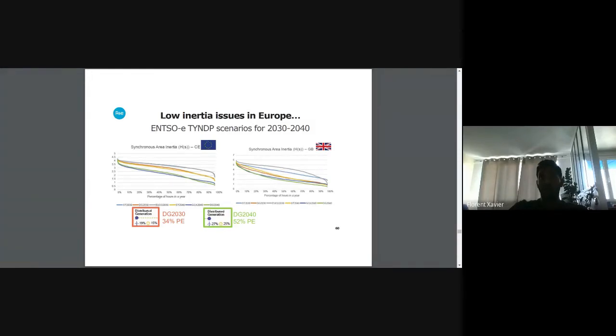The question is why grid forming, and why is fast frequency control not sufficient? Fast frequency control is a control where we use measurements, so we need time to measure frequency in order to inject power into the system. But if inertia decreases very fast, as we can see in this figure with near-zero inertia in Great Britain, with zero inertia the frequency will collapse quickly, in less than 100 milliseconds. So we need something to maintain voltage and frequency, and that's the grid forming solution.